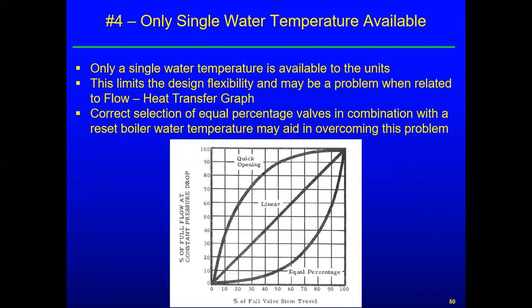Single water temperature available. A lot of simple systems, or ones designed by designers that don't really know what they're doing, let's say on a heating side, may design a constant water supply temperature of 160, 180 degrees. Well, it's hard to control the amount of heat transfer from that coil, especially as your valves start trying to shut. If you don't have the right type of valve, as illustrated below, with a quick opening, linear, equal percentage, you can lose controllability. So you can do a couple of things. Resetting boiler water temperature with outside air is probably the best thing to do, and certainly selecting the right style of control valves to make your control system work properly is important as well.